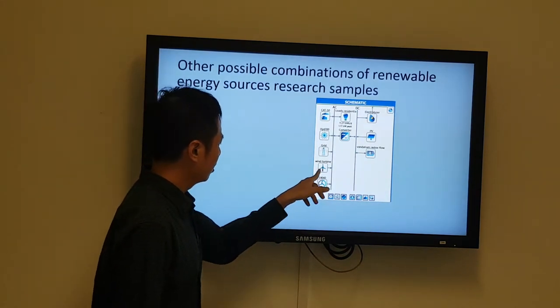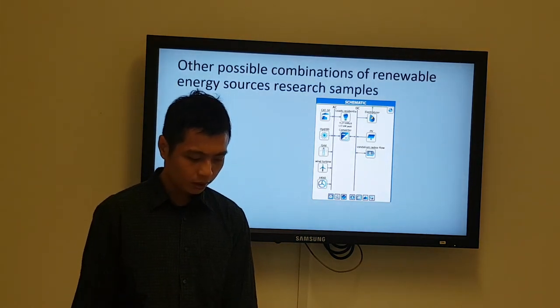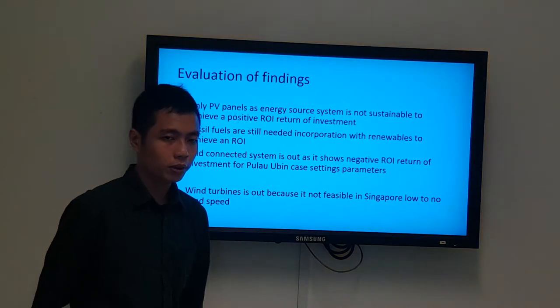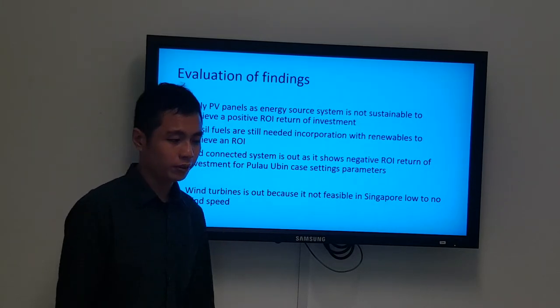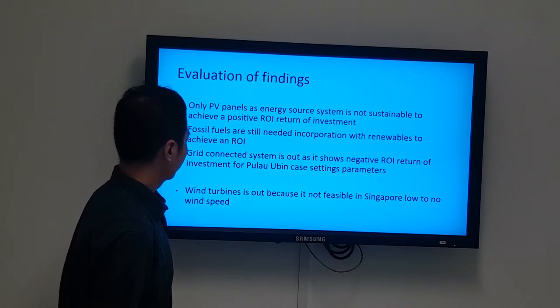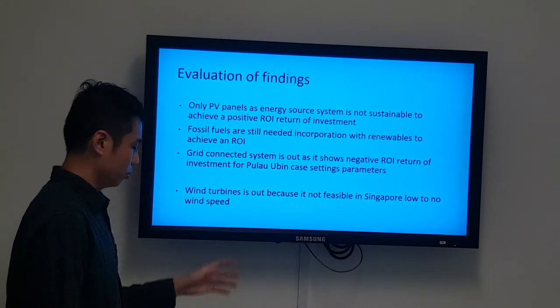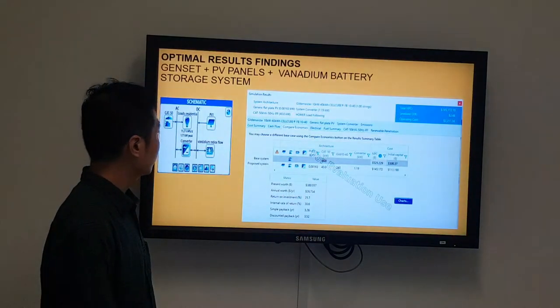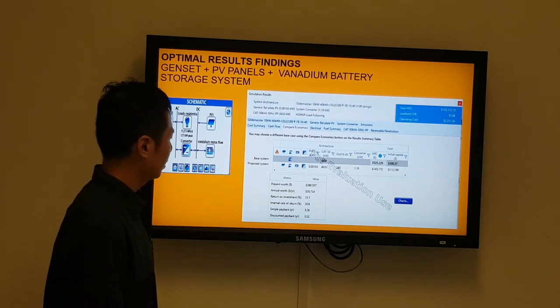Other possible connections on the software include hydroelectric, wind turbine, grid, electrolyzer with dispenser, battery, and solar panels. From all simulation tests, only PV panels to generate all energy needs is not sustainable, grid-connected gives negative ROI, and wind turbine is not viable in the Singapore context. The best optimal settings are the combination of generator sets, PV, and vanadium flow battery banks, which gives a return on investment of approximately 24%.